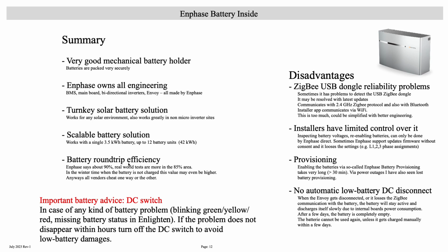So the round-trip efficiency, it's okay, let's say between good and okay. Enphase says it's about 90%, meaning you put 100% energy in from the solar system and get back 90% when you discharge the battery. In real-world tests at all my sites, we're talking more about 85%, which means 15% losses. That's all fine, because when we charge the battery we get free energy from the sun, and when we get a lot of sun we have too much energy anyway, so it's not a big problem.